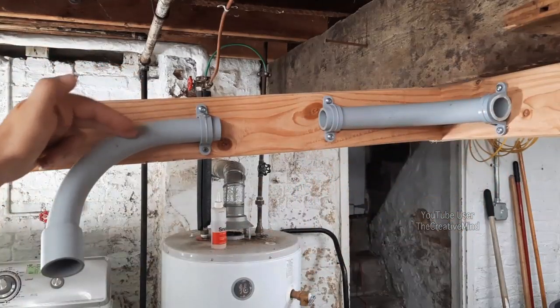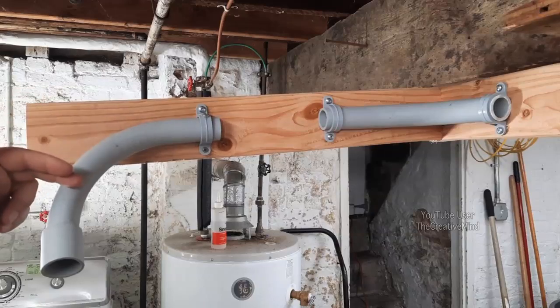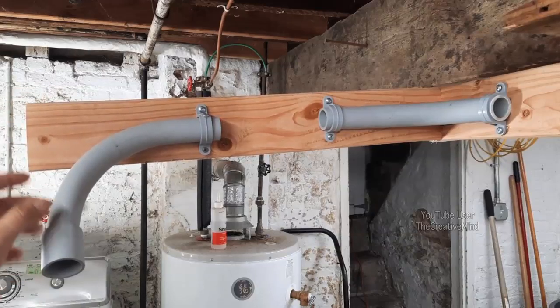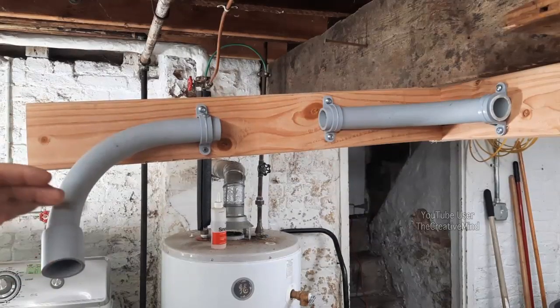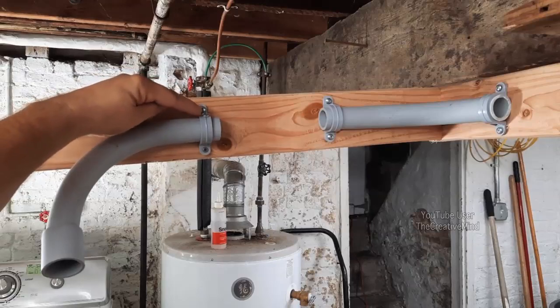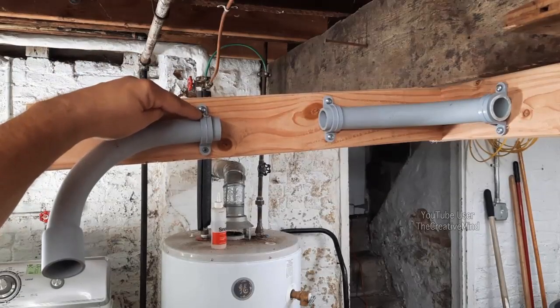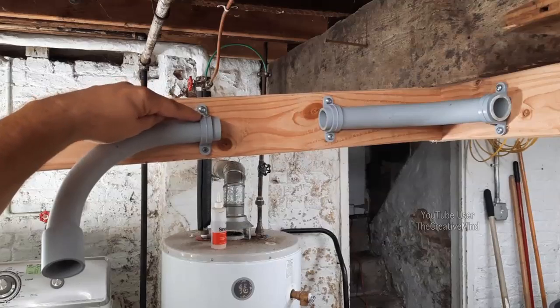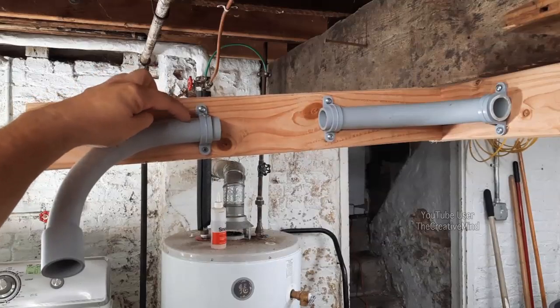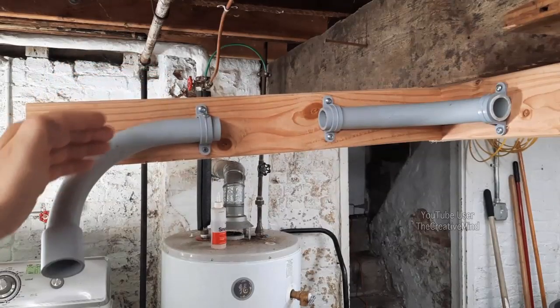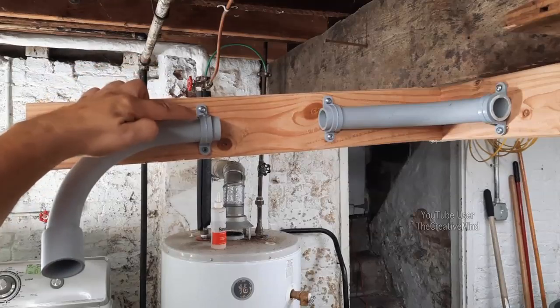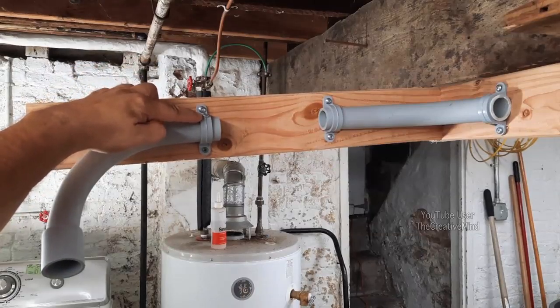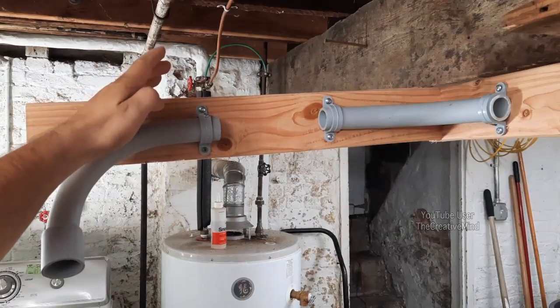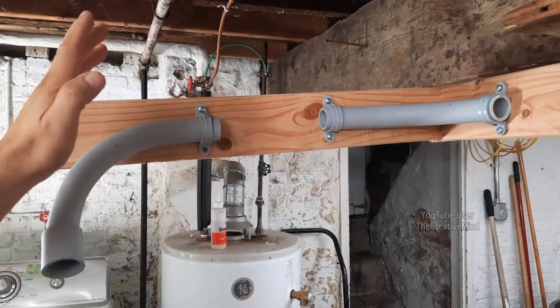Now this one here is kind of wonky because it's anchored downward, but this is just for the demonstration when I pull wire around the layout. You may notice there's a screw on top - this is something I'd never recommend, because the tip of this screw is penetrating into the conduit, and if you pull wires through this, there's a chance the wires can skin through the screw and cause electrical shorts around your layout, which you don't want.